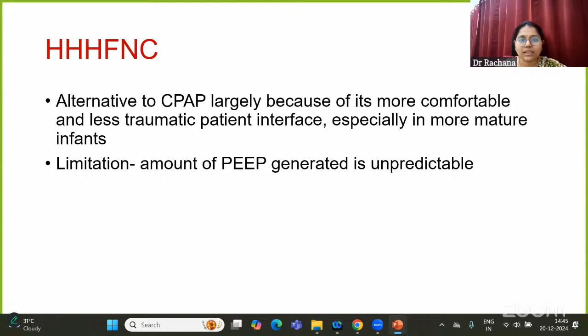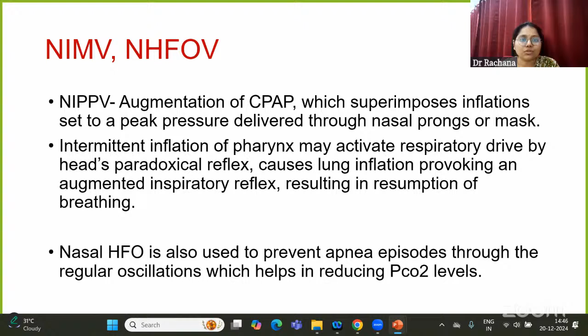Even the newer modes like NIPPV and nasal HFOV have also been used for the apnea of prematurity. In NIPPV, there is augmentation of CPAP, which superimposes inflations set to a peak pressure delivered through the nasal prongs or mask. There is an intermittent inflation of the pharynx, which activates the respiratory drive by Head's paradoxical reflex, which causes lung inflation, provoking an augmented inspiratory reflex, resulting in resumption of breathing, and it terminates the apnea. Nasal HFO can also be used to prevent the apneic episodes through the regular oscillation, which helps in reducing the PCO2 levels.